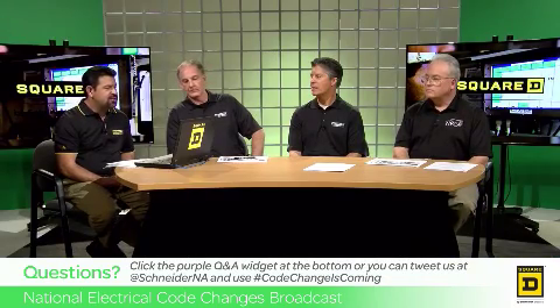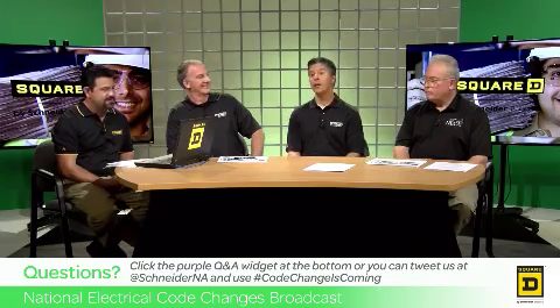We have one for section 110.16(B) in reference to fault current on the new label. Is the current a maximum available fault current or a real available fault current number? So this is the real available fault current number. This is the huge challenge. It's not the number the utility gives you, and it's not assuming an infinite bus and using the transformer. This is really calculating based on an accurate number from the utility through the transformer and what you have based on your conductor length. What is the real available fault current? That is the challenge here. Wouldn't you guys agree? Absolutely.